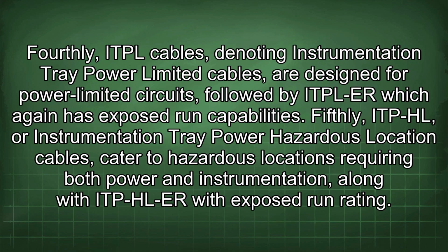Fourthly, ITPL cables, denoting instrumentation tray power limited cables, are designed for power limited circuits, followed by ITPL-ER, which again has exposed run capabilities. Fifthly, ITP-HL, or instrumentation tray power hazardous location cables, cater to hazardous locations requiring both power and instrumentation, along with ITP-HL-ER with exposed run rating.